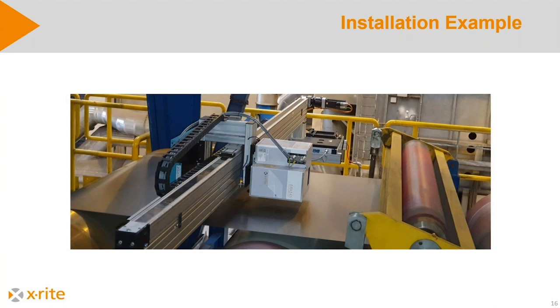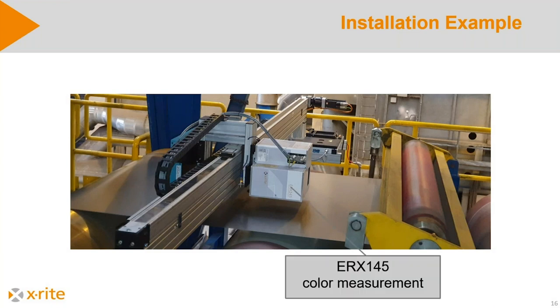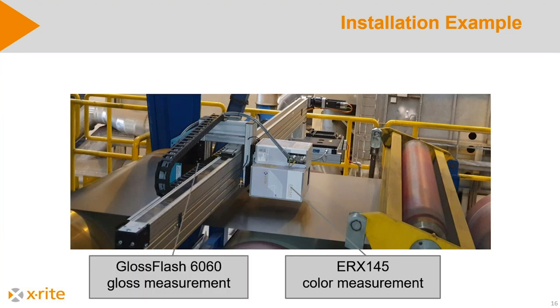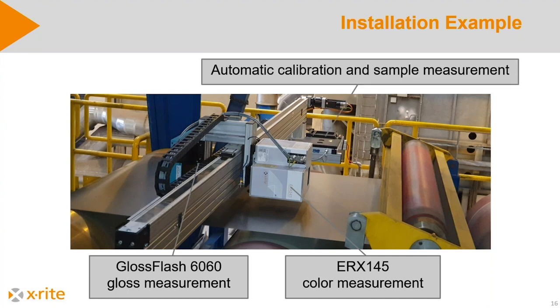So this is an installation which we have made recently. We have here the ERX 145 instrument to measure the color. On the back side, you see the gloss flash, which is the measurement for the gloss on 60 degree. And at the back, you see this automatic calibration station. The calibration tiles are closed with a lid so that there is no dust on it, and when the instrument moves over, it opens to calibrate the system.